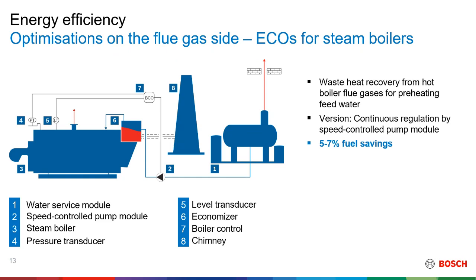So in a setup where we have an economizer, water will flow from the water service module, feed water tank, through the feed water pump and into an economizer, which is a heat exchanger, and heat will be moved from the flue gas which is leaving the boiler and into the water that is going into the boiler. And there you're actually saving some fuel by heating up the water that is going into the boiler.